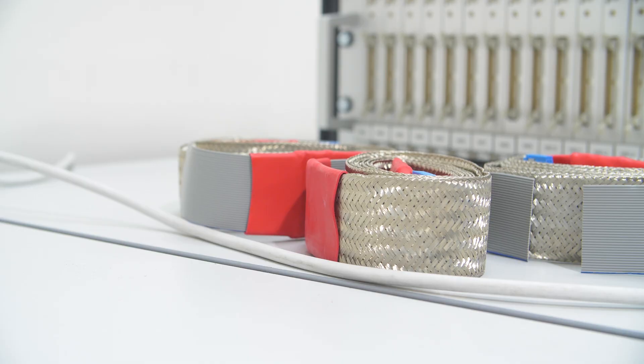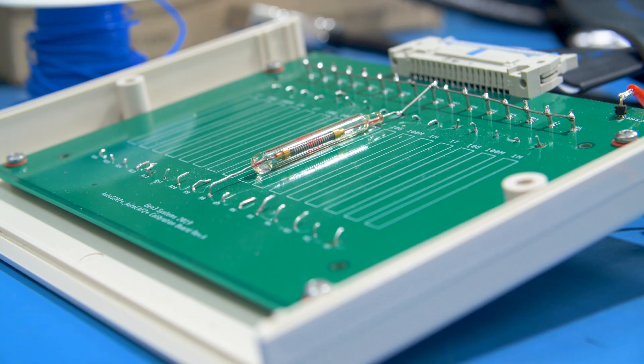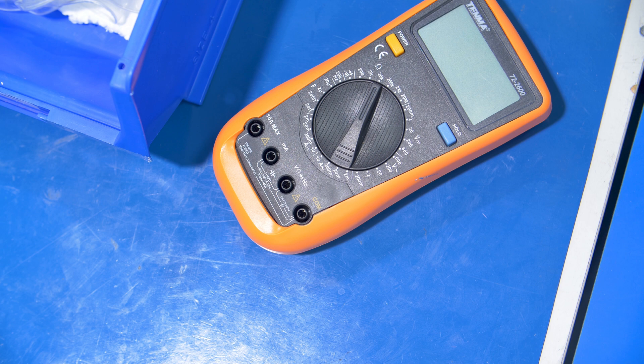We can currently test up at 1250 volts and obviously due to the complexity now with PHEV vehicles and the circuitry, that's obviously a necessary function. You need to test the boards at very high voltage.